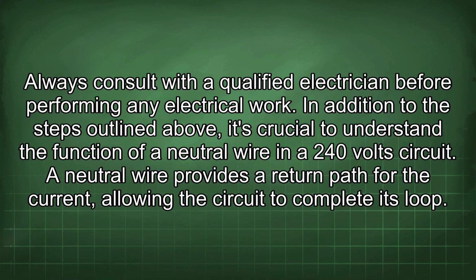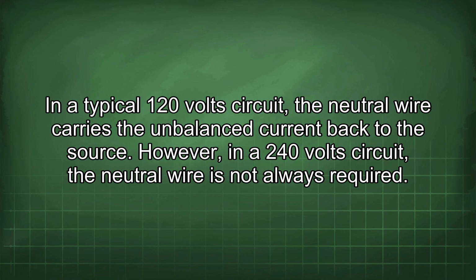In addition to the steps outlined above, it's crucial to understand the function of a neutral wire in a 240-volt circuit. A neutral wire provides a return path for the current, allowing the circuit to complete its loop. In a typical 120-volt circuit, the neutral wire carries the unbalanced current back to the source. However, in a 240-volt circuit, the neutral wire is not always required.